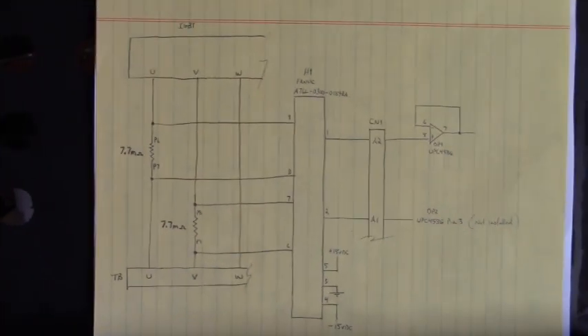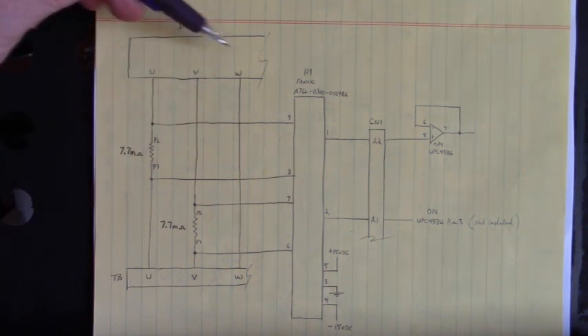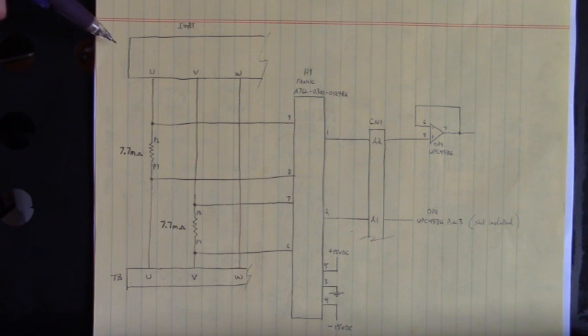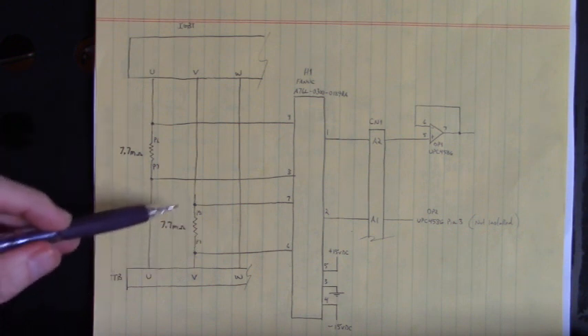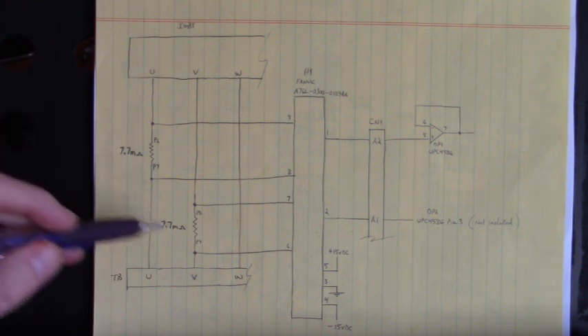It's starting to get dark outside, so we've got to kind of hurry up with this explanation of testing the FANUC isolation amplifier module. And that's this device right here. Now, up here is the IGBT inside that FANUC servo amplifier. And also inside that FANUC servo amplifier unit are two resistors.